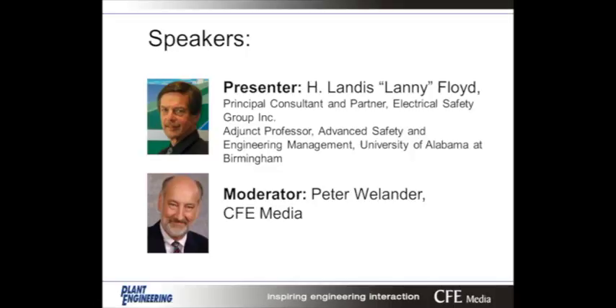So for most equipment that's under 600 volts and above 240 volts, there may be an exposure to an electric arc or contact with electric current that could result in a shock. So PPE should be part of your control measures unless you've analyzed it specifically and determined it's not necessary. That would be, for example, for an arc flash event, if you've done the analysis and determined there's no arc flash hazard, or done a shock hazard analysis and determined that due to the construction of the internal circuitry there's no likely way to contact a bare exposed part. Then you may consider that PPE may not be required. But unless you've done that work to determine that, my answer would be you better be thinking about making sure you have the PPE available and on.